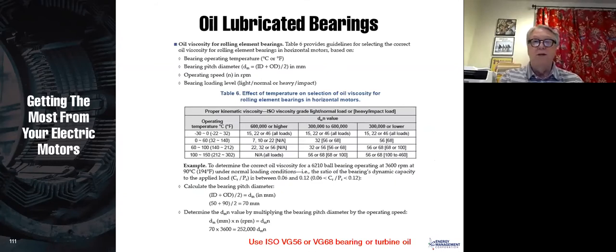One of the stories, you can change oils. I remember when I was the director of engineering for Geneva Steel, and we had actually 3 motors that we had bought, used, and put them in. They were vertical motors, and they had an oil bath, and we just couldn't get that oil viscosity down. And finally, we drained the oil and put in Royal Purple, which of course is a 100% synthetic oil. And I was quite frankly amazed that oil temperature came down much faster, or much more than I expected that it would. So it's very important with oil lubricated bearings that you use oil that's rated for the temperature that you're going to be running.